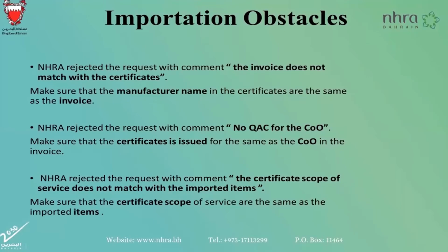NHRA rejects the request with the comment that the certificate scope does not match the imported item. Always make sure that the certificate scope covers the imported item. NHRA rejects the request with the comment that the certificate is invalid. Even with a valid date, you should check your certificate before submission to avoid submitting an invalid document.